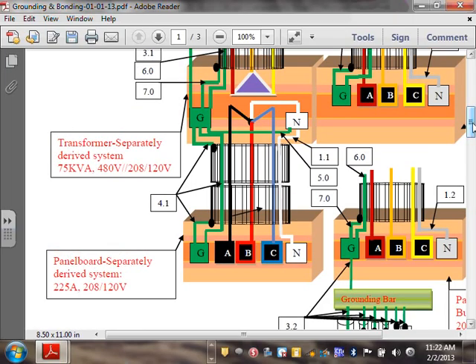You can either do the main bonding jumper inside the transformer and pull a neutral, then you don't bond it in this panel, or you can do your bonding inside this panel, but you can't do it on the neutral. Typically what they do, the best way to do it, is inside the transformer. We do have access to the transformer though, right? That's our transformer. We own and operate it and we bought it. So typically you go to the X0 here and you tie it to the ground right here.